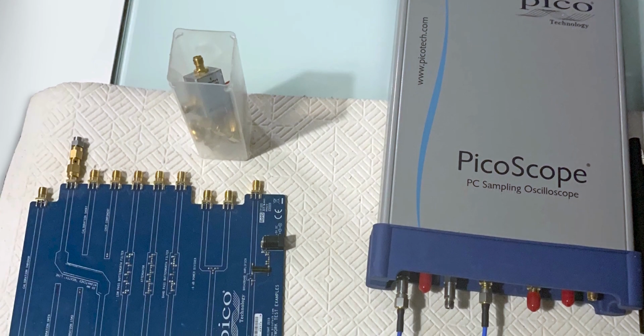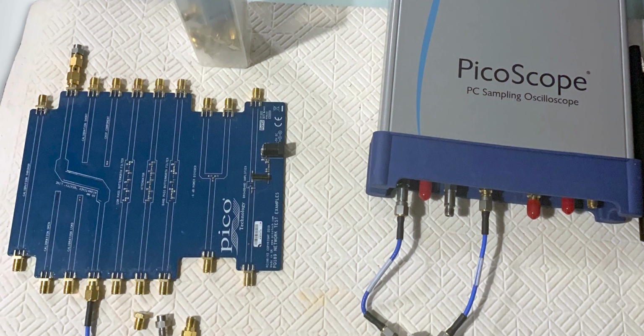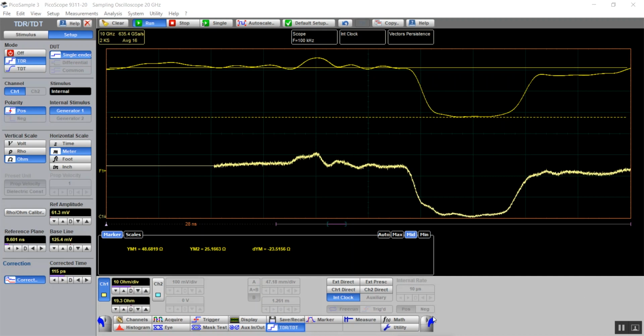In this demo, we are characterizing a 50 ohm mismatched impedance Beatty line on the network test examples board, part of the RF network training kit. In my setup, I'm using the positive pulse and measuring both impedance and distance of the mismatched line.